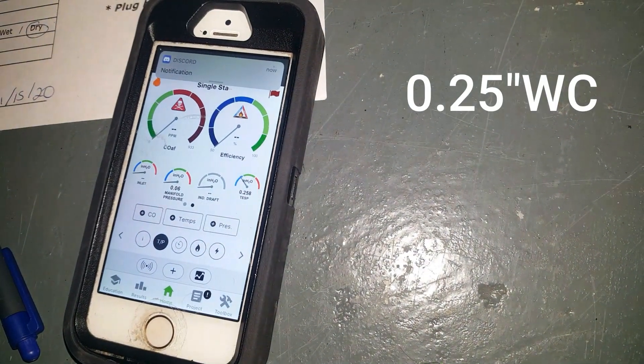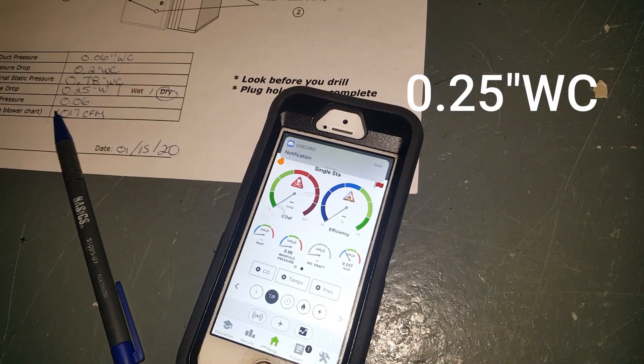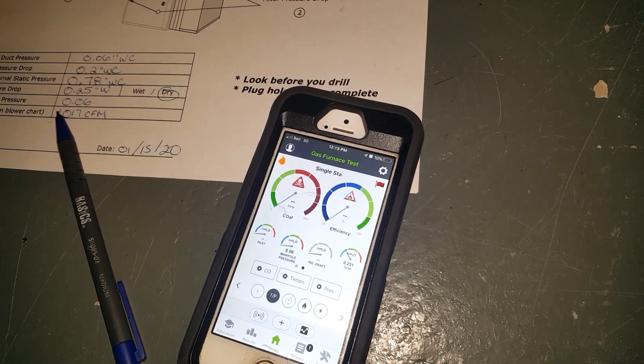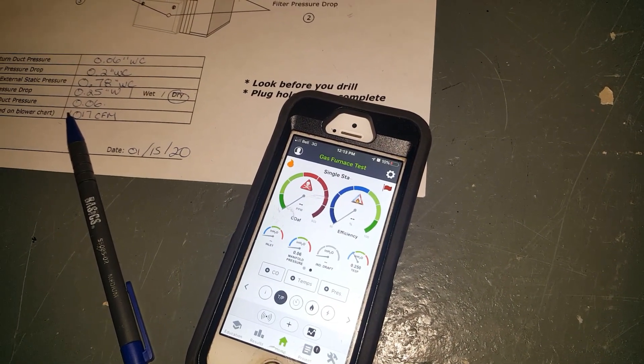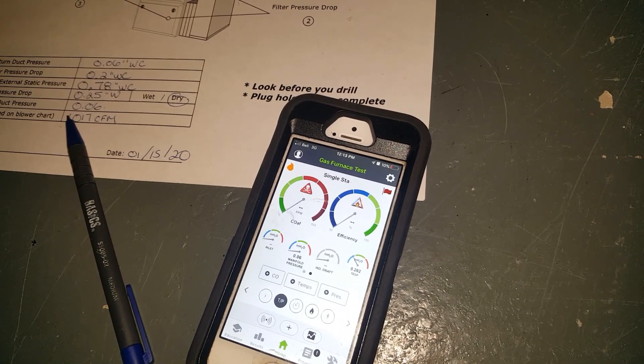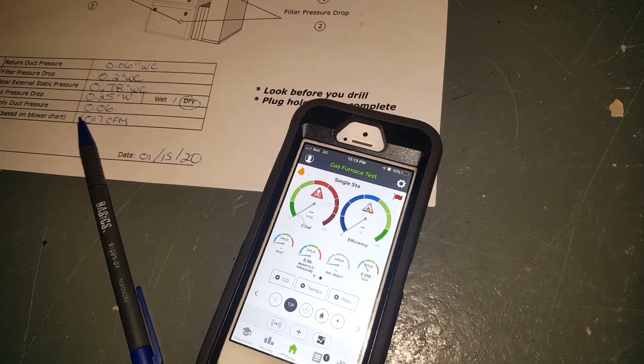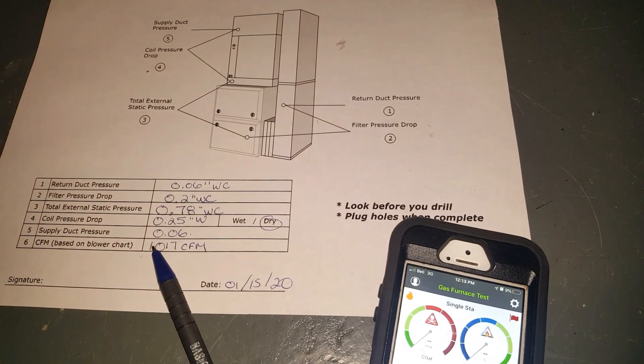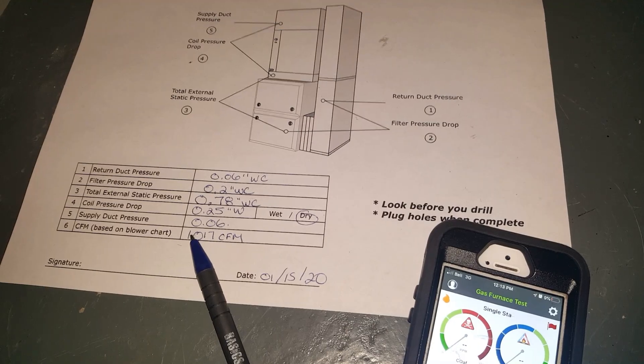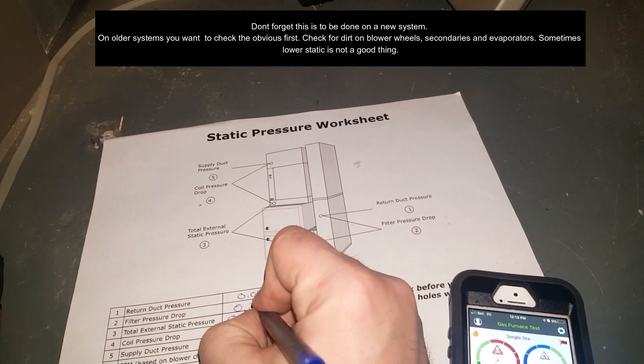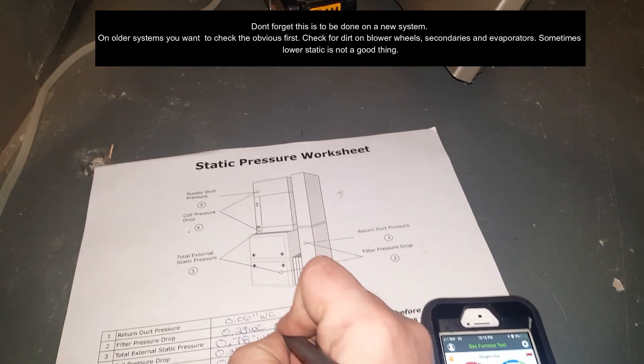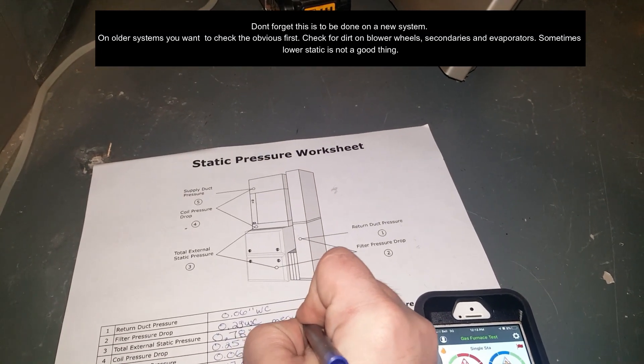Okay guys, so with the new filter in there I got 0.25, a little bit more of a drop on this one, probably because it's a Merv 16 and it's got more pleats in there. But overall, there's the calculations, and that's how we take total external static. I'll just write here Merv 16.